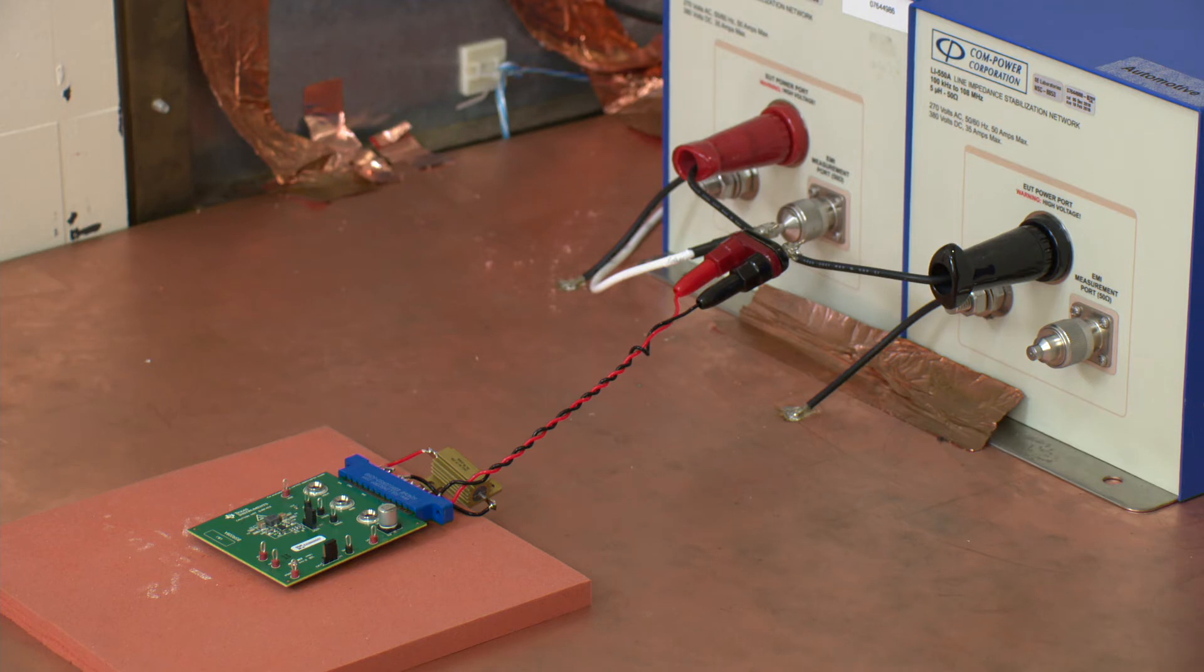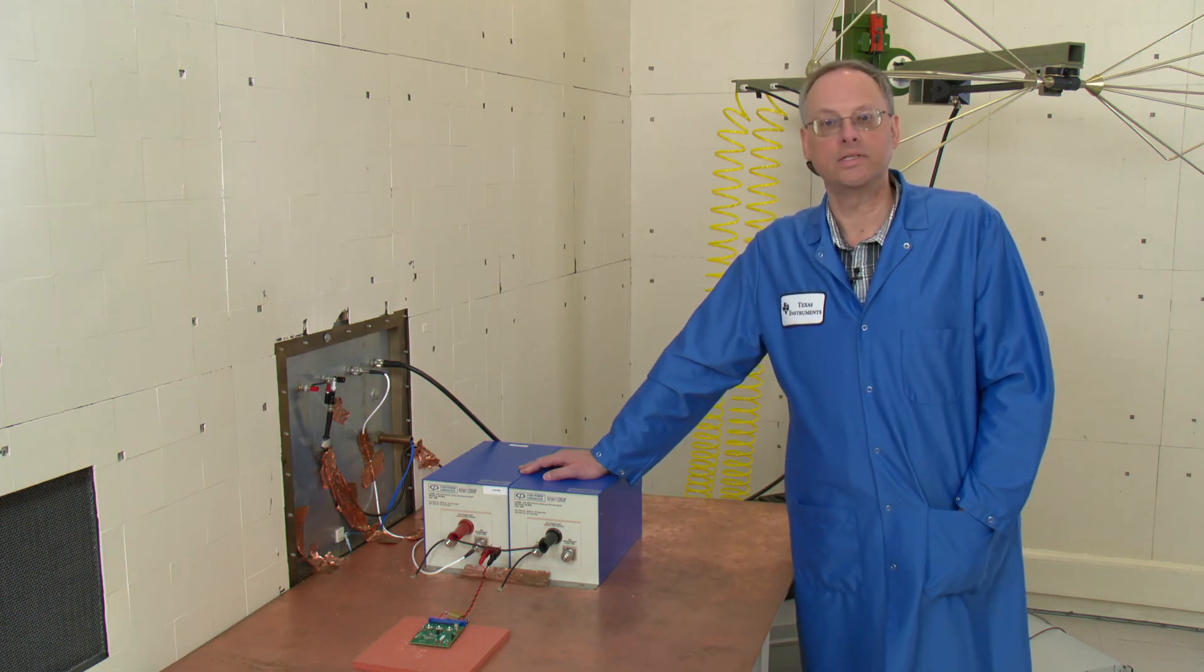As you can also see, our DUT is separated exactly 200 millimeters away from the input to LISN, which is part of the specification. And our load resistor is connected very close to the DUT, so any noise generated in that resistor will not be counted and included in the scan. So let's go back in the lab and run the scan.